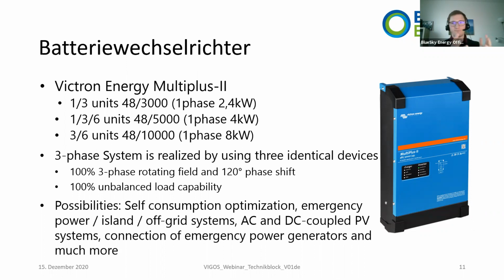Inside the system we have different units or numbers of battery inverters, and a 3-phase system is realized by using 3 identical devices. With the 3 identical devices, we fulfill a 100% 3-phase rotating field with 120 degrees phase shift, and 100% unbalanced load capability, also in off-grid mode. So also only one phase can be loaded with full power.